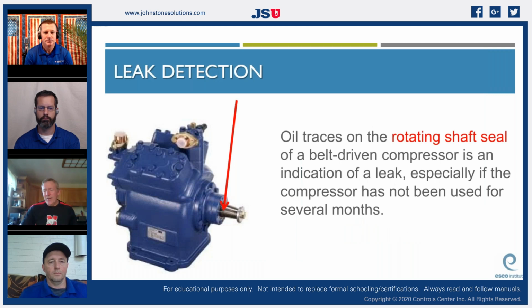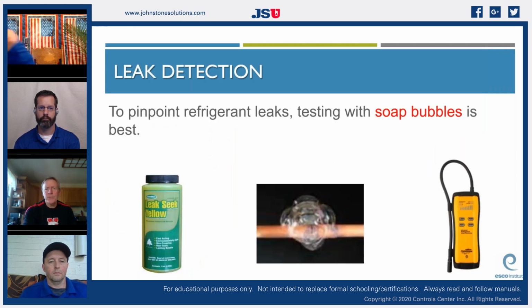I've seen this on more tests than I can count. The traces of oil. Rotating shaft seal is where they tend to leak on a belt drive compressor, especially one that hasn't been operating for a while. So the shaft seal will be the most primary place for the leak. And it's probably actually true. And we also pinpoint leak with soap bubbles. It's kind of redundant, but this is the way I've always found leaks, by the way.